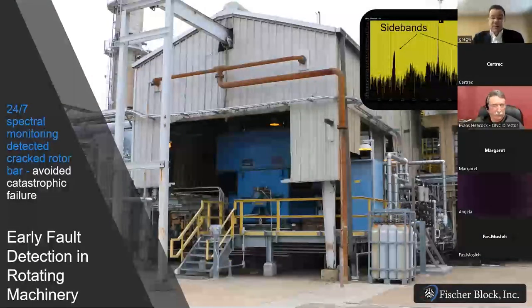And this one here is a very important use case as well. A very critical asset here is a motor and pump at a chemical plant. And our platform is doing 24/7 continuous monitoring of the current draw from the grid into that motor. And the distortions on that current signature are very consistent, and they provide an indication here. You can see those side bands on either side of the fundamental, and the spacing plus or minus on that 60 hertz indicates what slip the motor has versus the grid, because the motor's running a little bit slower than the grid.